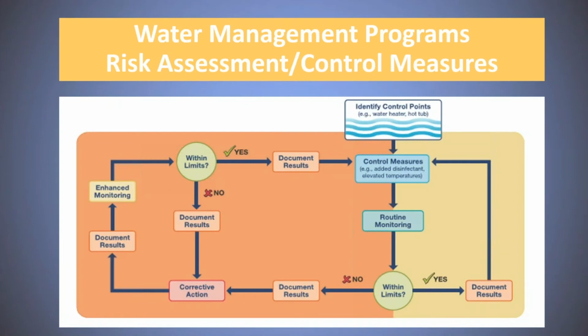Until the next sample point comes along. But if it's out of limits, documenting those results, and understanding what corrective actions should be put into place is a big part of what we do. So think about a dead leg in a piece of pipe where the water is not circulating. Depending on the temperature, if it has Legionella growth in it, at some point when the system is drained or there's low pressure, that Legionella could be pulled out into the rest of the system. So understanding when your exposure happened, that you took a measurement and said there's a problem here, what are we going to do now to fix that? A lot of times our healthcare customers lean on us to say, we got a bad reading, what can we do to mitigate this going forward?